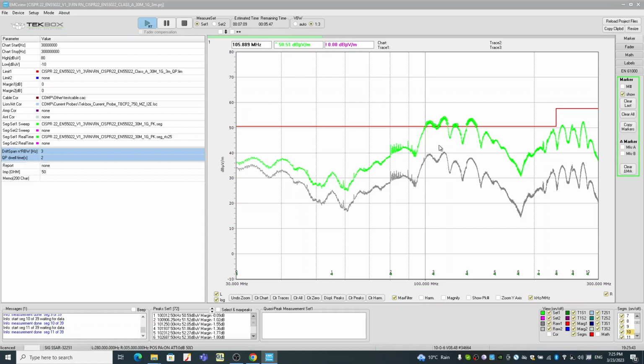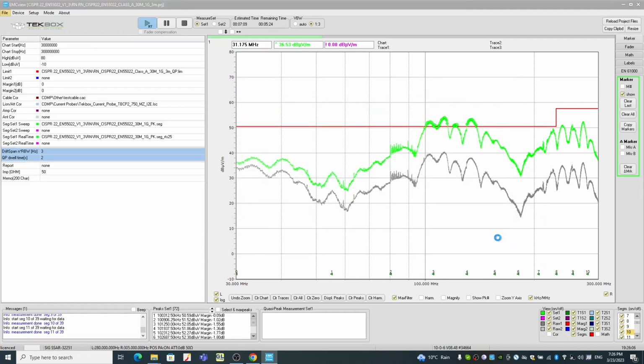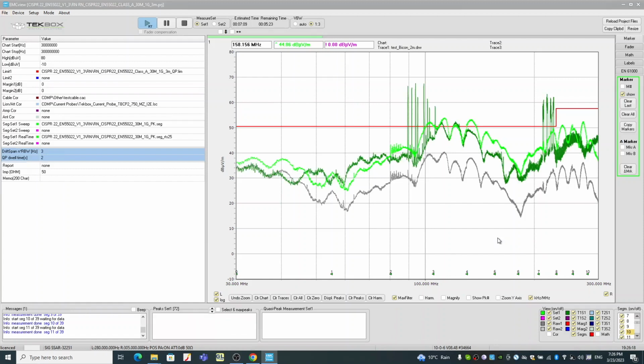It does look very similar to the far field measurement we had using the Bicone antenna. But let's just have a comparison, because we can do that, right, using saved files. So if I go to utilities and then load reference trace, and I'm going to select trace 1 as test Bicone 2 meter, which is the test we just did using the Biconic antenna. So that's loading the far field measurement we performed, and you will see it takes some time, and that's it.